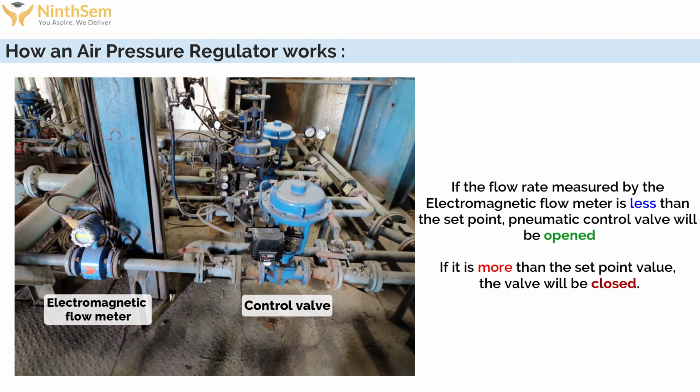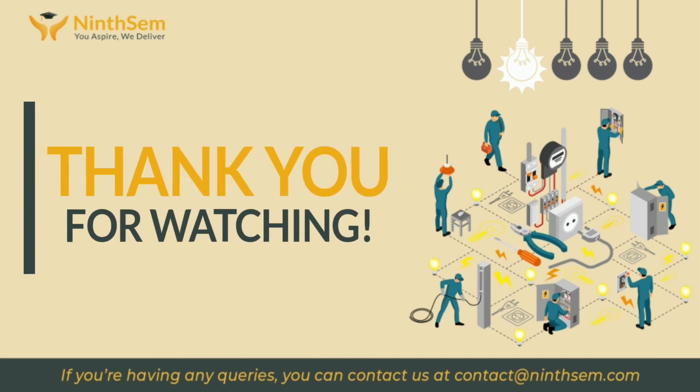In this way, our spray controller system, our secondary cooling system, can be achieved to maintain the desired solidification of the billet in the casting process. In this way, billet casting has been done. So this concludes a case study of the secondary cooling system, which includes two transducers. One is the magnetic flow meter, another is the current to pressure converter. The application part I explained is in the steel melting shop. Okay, thank you.